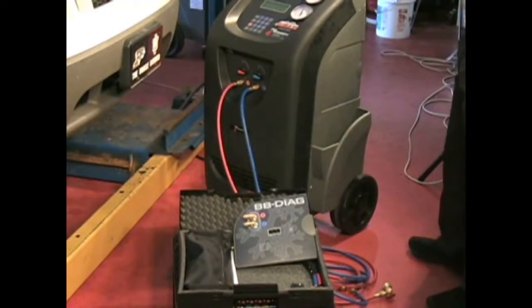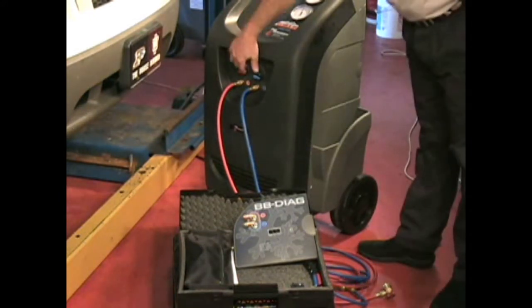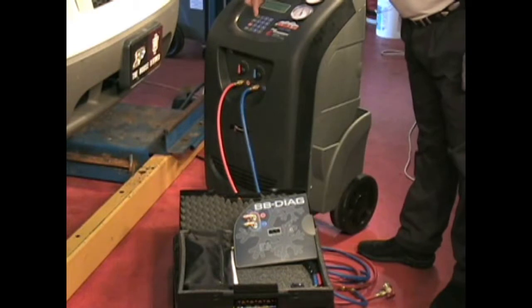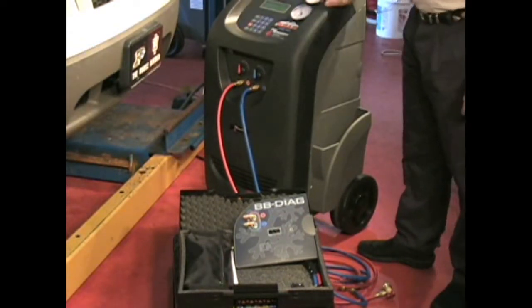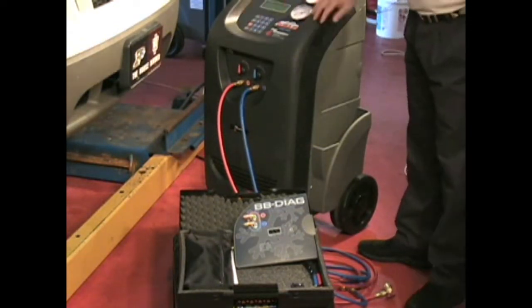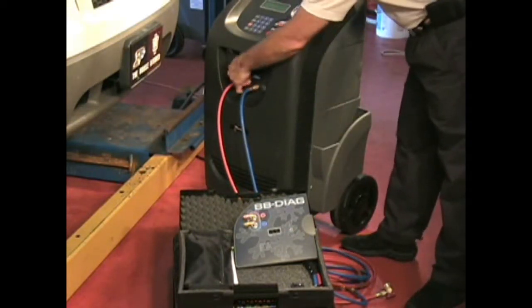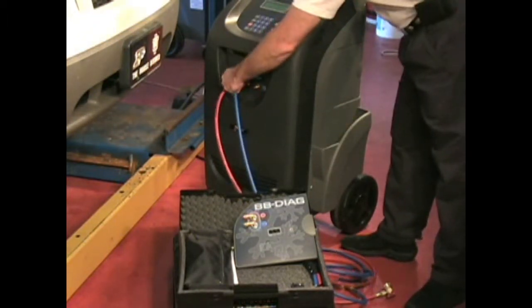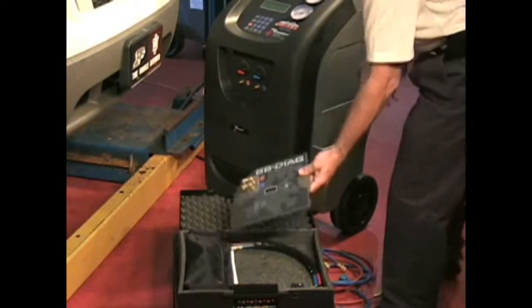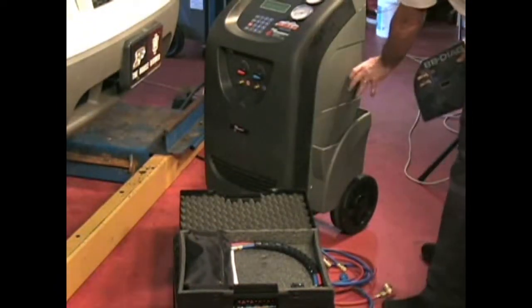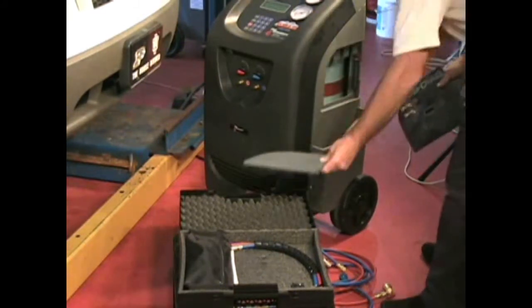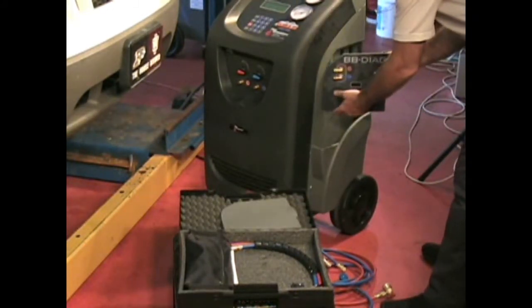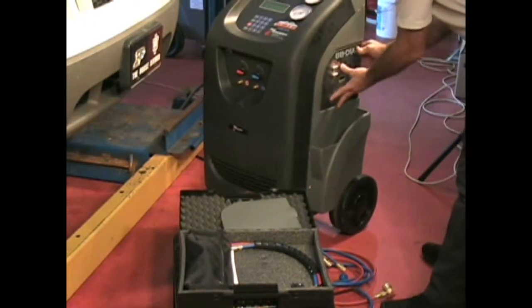To install the DM300, first recover any refrigerant in the system hoses using assisted procedure, then recovery. Allow the machine to pull the hoses down to 0, then press Reset. Disconnect the hoses. Now remove the right side panel and place the diagnostic module in its place. To help hold it in its slot, we suggest placing a small self-tapping screw through the back side of this plastic housing into the DM300 plastic.